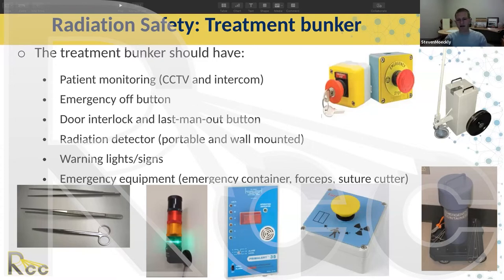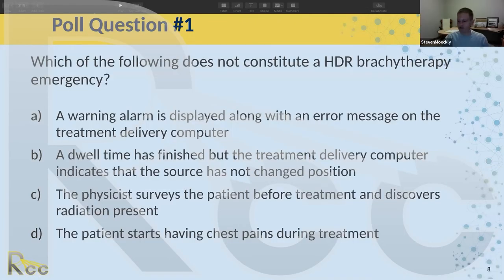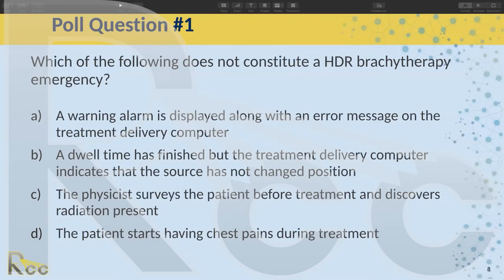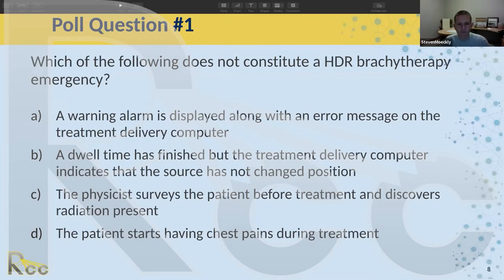Poll question one: which of the following does NOT constitute an HDR brachytherapy emergency? The options are: a warning alarm displayed with an error message; a dwell time has finished but the treatment delivery computer indicates the source has not changed position; the physicist surveys the patient before treatment and discovers radiation present; or the patient starts having chest pains during treatment.